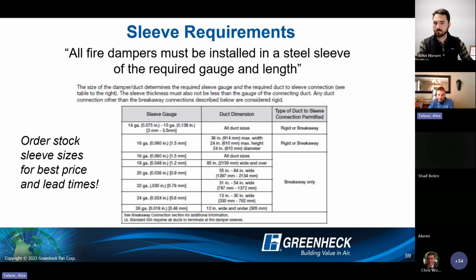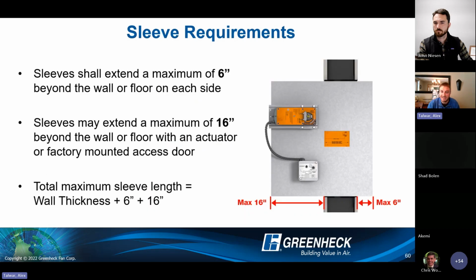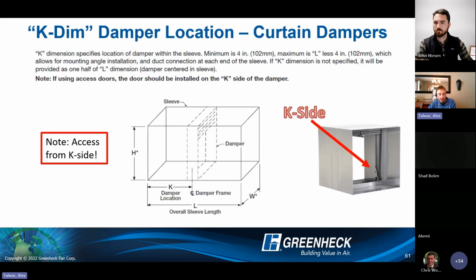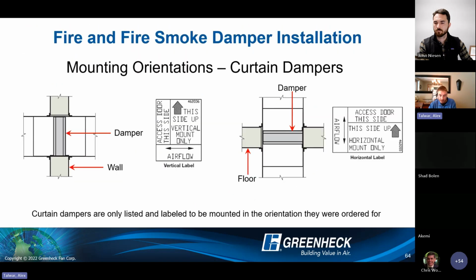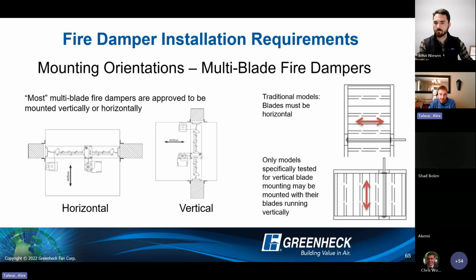Installation stuff. It's important that the fire or fire smoke damper is in a sleeve, the correct sleeve. I'm not going to go deeper than that, but just be aware that the damper itself does need to be in a sleeve to facilitate the installation. That sleeve has some requirements in terms of how far out of the wall it needs to come. So 6 inches max, unless we have an access door or actuator, then we can do 16 inches, but then we do have to terminate that sleeve. And if we're continuing ductwork, we'll need to make a breakaway connection there. I'll skip over this part here. Mounting orientation we talked about already.